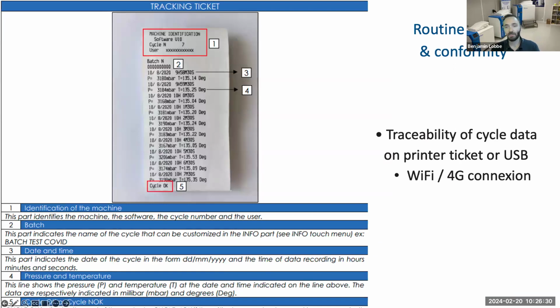For the traceability ticket that is being printed, we have it either as a ticket or through USB. This ticket can also be personalized, customized, depending on the different regulations. However, we have 5 major pieces of information on it. First, the name of the machine, the identification number of the machine. Second, the number of the cycle, the date and time of the cycle, information related to the temperature, and whether the cycle is okay or not okay. If the cycle is not okay, then the machine will lock and the local partner will have to intervene for a maintenance. Next slide, please.